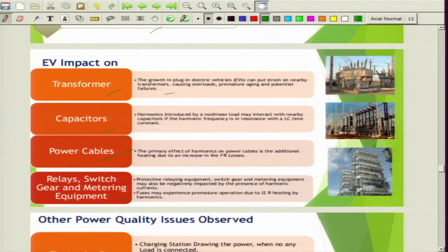There could also be an impact on the operation of protection devices such as circuit breakers, relays, distance relays, and overcurrent relays. When electric vehicles are present in the system, they may cause varying power flow, posing a threat from the perspective of the protection system. What may happen is when the relay is supposed to operate it may not operate, and when it is not supposed to operate it may operate. This mal-operation of relays can lead to serious protection threats.